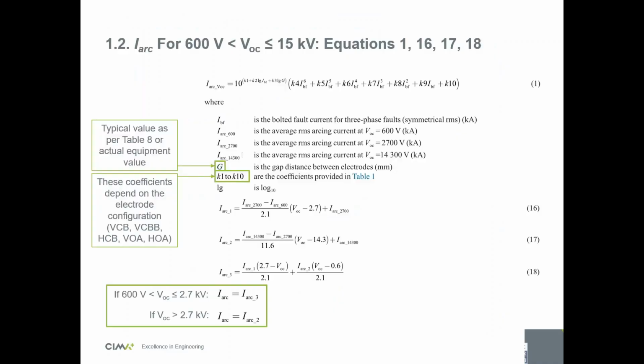Once you have the electrode configuration, if your voltage is above 600 volts, you have three arcing currents to calculate first: IARC 600, IARC 2700, and IARC 14.3 kV. You always calculate three arcing currents with this big equation. It's much more complex than the 2002 version. You have a bunch of K factors, K4, K5, K6, which are based on your electrode configuration, so they change with it. Once you have these three IARCs, IARC 600, IARC 2700, and IARC 14300, you need to interpolate these values.